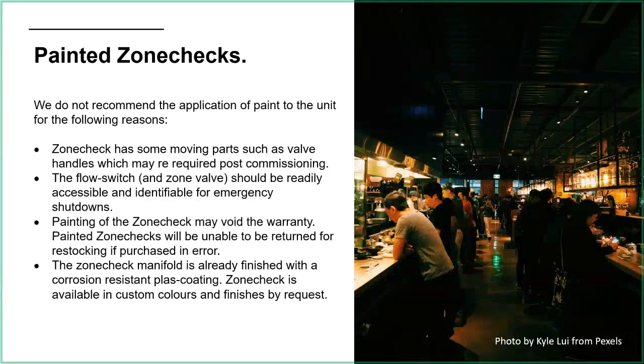First of all, we do have some moving parts, such as the valves either side of the pump. So if the pump ever needs to be replaced, we need access to those. Same with the zone valve. If the zone valve has been painted, that wouldn't be recommended, because we need to get to it. There's also an indicator paddle on there, which is important to show you whether the valve is open or closed. The flow switch and the zone valve should be readily accessible and identifiable for emergency shutdowns. Our zone check is not important for emergency shutdowns, but the flow switch is. So if that's now got the same colour as the rest of the ceiling, it's going to be harder to spot.